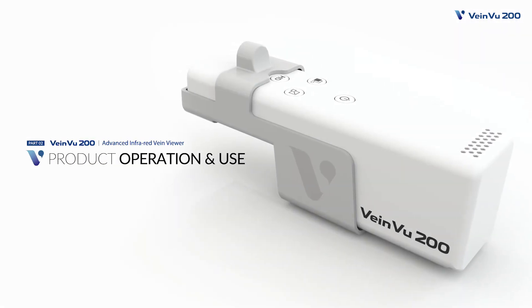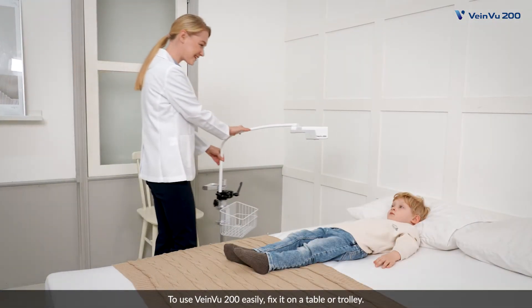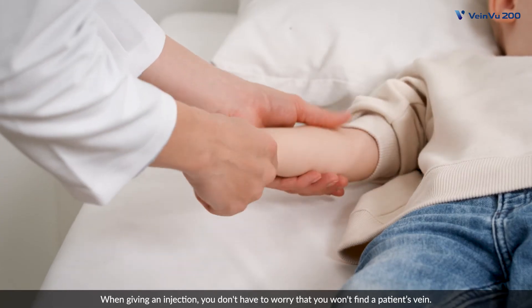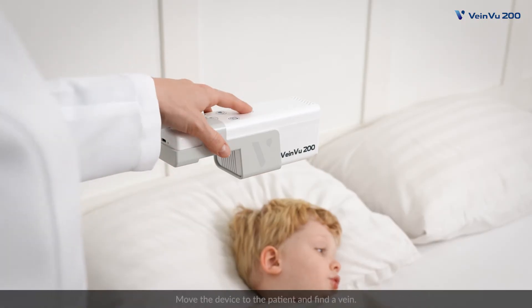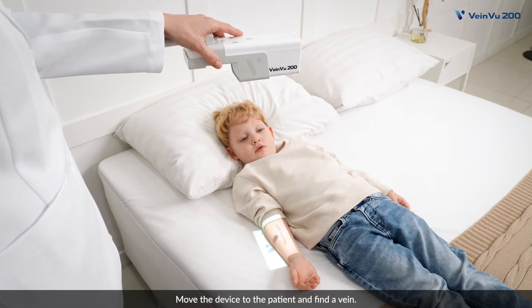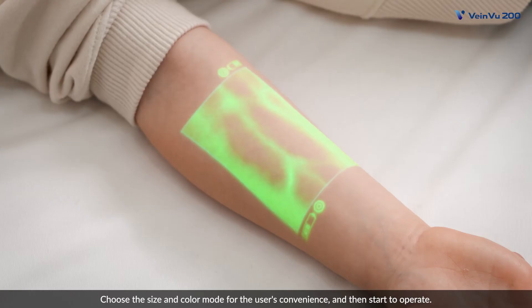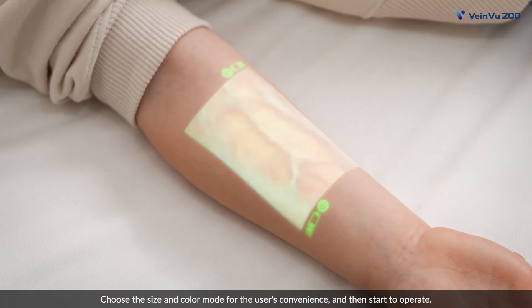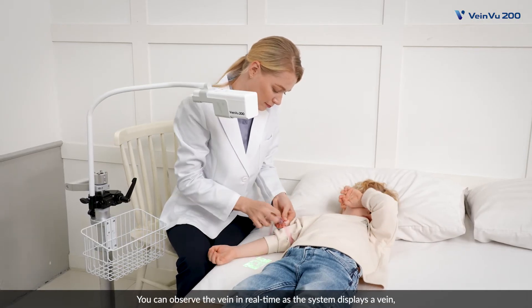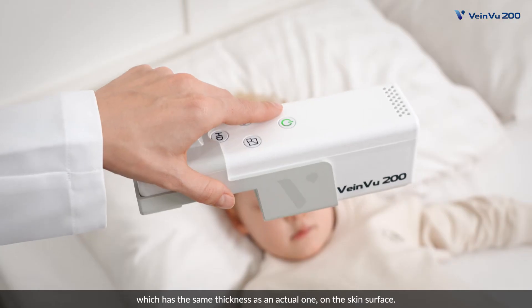Product Operation and Use. To use VeinVu 200 easily, fix it on a table or trolley. When giving an injection, you don't have to worry that you won't find a patient's vein. Move the device to the patient and find a vein. Choose the size and color mode for the user's convenience and then start to operate. You can observe the vein in real time as the system displays a vein, which has the same thickness as an actual one on the skin surface.